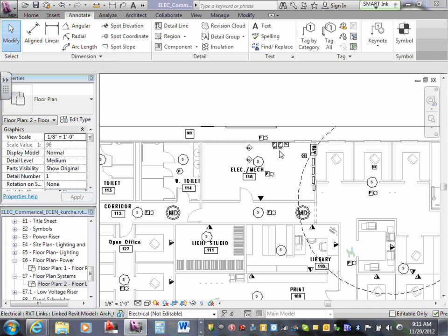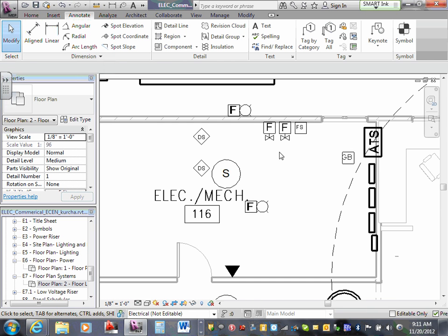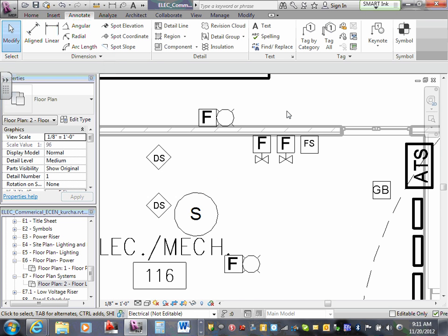That right here, that's where our main fire protection is. Flow switch is obviously just a sensor of when there's flow in the fire protection, so the sprinkler system. If one of the sprinkler heads goes off, then that thing will sense flow through the fire protection system and send an alarm back to the fire alarm panel.